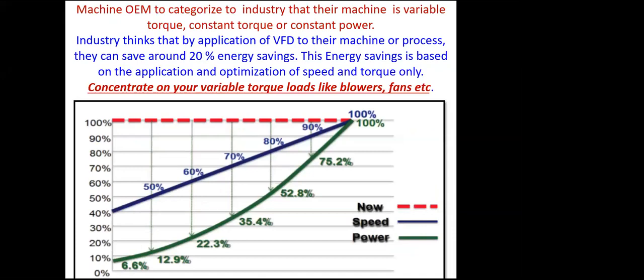Especially if you are able to, on a 1500 RPM motor, reduce the RPM by 10%, you are able to save around 27% of the power, thanks to the cube law, especially applied to fan applications, centrifugal fans and even axial flow fans. This energy saving is possible on these centrifugal fans.